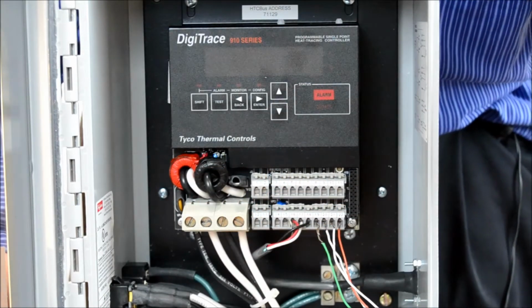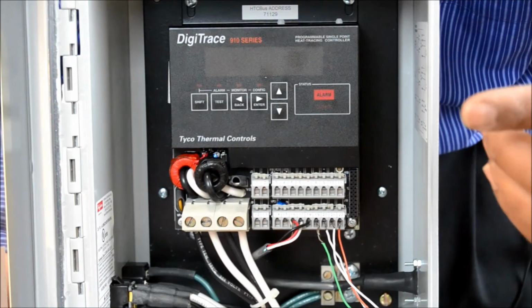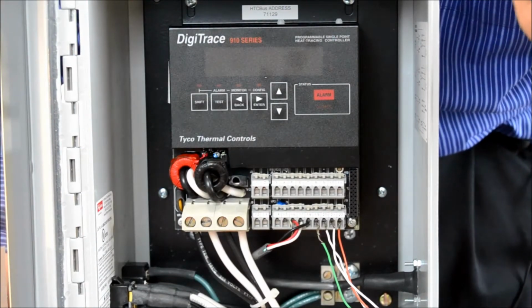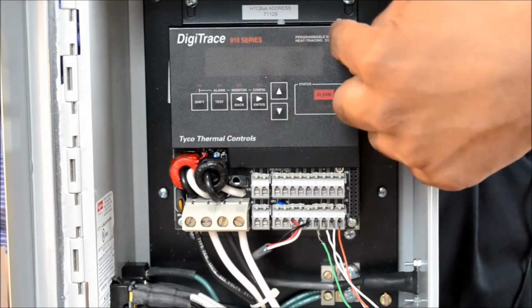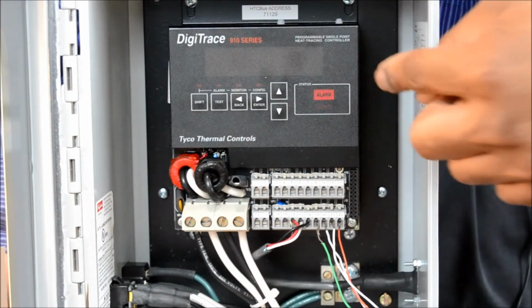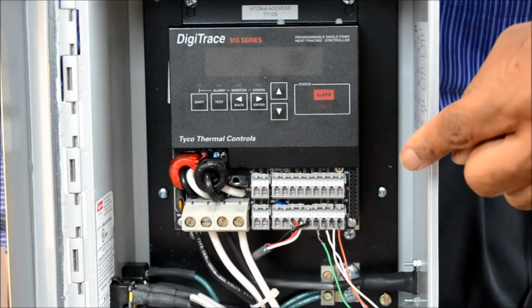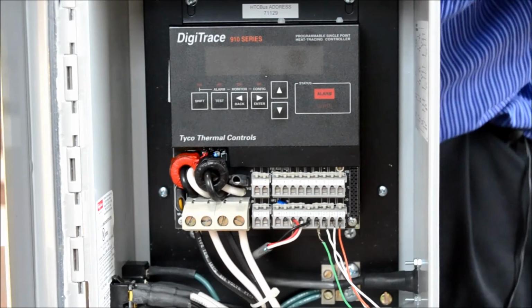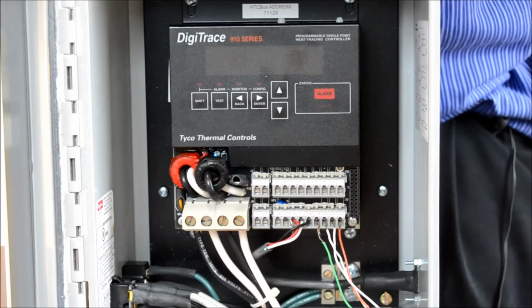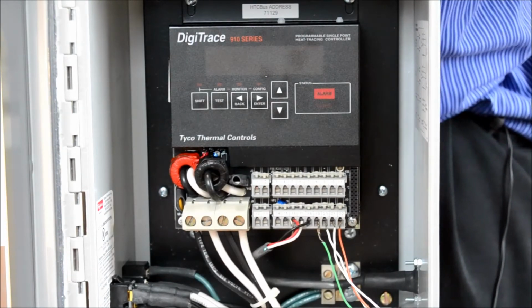Now, like I said before, this is de-energized. If this was energized, I wouldn't be opening this up, for one. And two, you would have a running display on the actual circuit board here. So you have your incoming power here, your outgoing power to your heat trace, and then your RTD. And essentially that's all of the components that are inside and how that works.